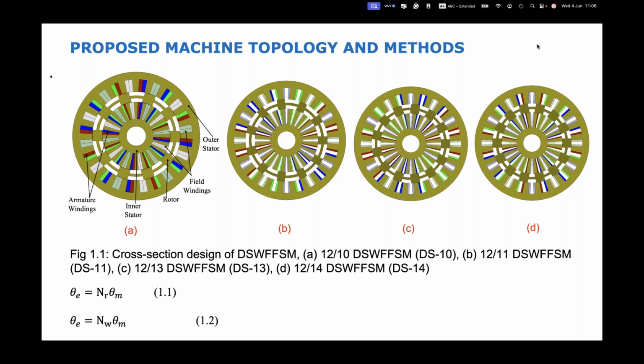These 4 different topologies are equal in size and have the same rating. The only difference between the 4 of them is the number of rotor poles. Figure 1a has 10 rotor poles, B has 11 rotor poles, C has 13 rotor poles, and D has 14 rotor poles. All these 4 models will be modeled in 3D finite element analysis under different winding configurations, and the nature of their back-EMF will be investigated and compared.